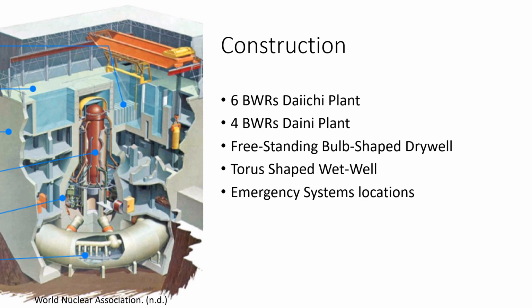The shape of the reactor was a freestanding, bulb-shaped dry well with 30 millimeters of steel backed by concrete. A wet well constructed below was torus or donut-shaped with 3,000 cubic meters of water as an energy-absorbing agent should a reactor accident occur. This design protected against a loss of coolant accident of any size of piping in the plant. If a loss of coolant accident were to occur, steam from the dry well would travel through the vent lines of the primary containment and into the suppression chamber or donut to condense.